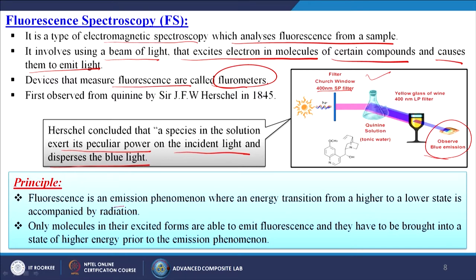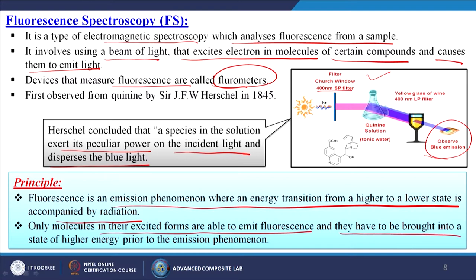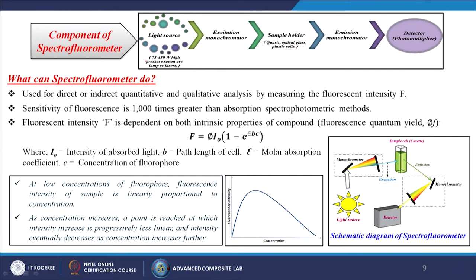Principle: fluorescence is an emission phenomenon where energy transition from a higher to a lower state is accompanied by radiation. Only molecules in their excited forms are able to emit fluorescence and they have to be brought into a state of higher energy prior to the emission. Components of a spectrofluorometer: light source — generally a 75 to 450 watt high pressure xenon arc lamp or lasers. Then an excitation monochromator, then a sample holder either made of quartz, optical glass, or plastic cells. Then an emission monochromator and lastly a detector or photomultiplier.